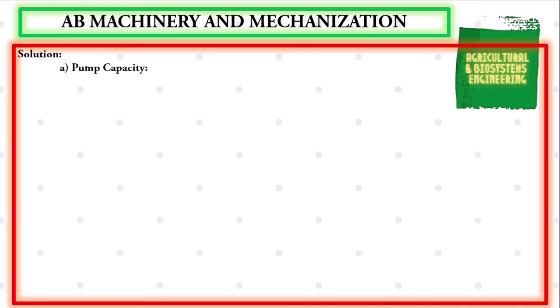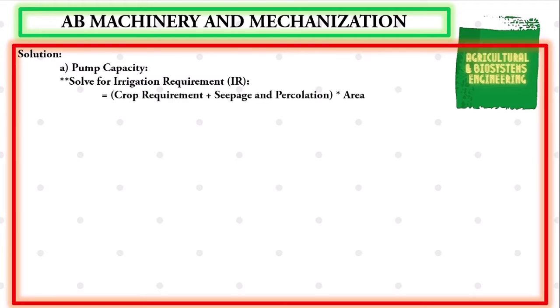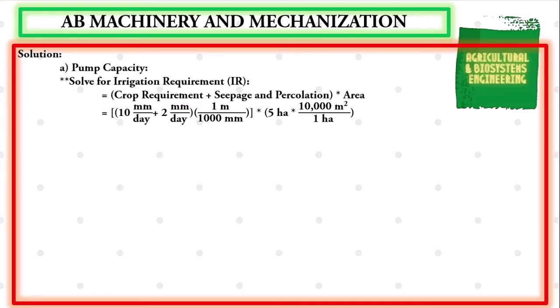The first value we are going to solve is the pump capacity. We begin by solving the irrigation requirement (IR). Using the formula: IR = (crop requirement + seepage and percolation) × area. Substituting: (10 mm/day + 2 mm/day) ÷ 1000 mm/m × 5 hectares × 10,000 m²/hectare. The millimeter and hectare units cancel, giving IR = 0.012 m/day × 50,000 m² = 600 cubic meters per day.